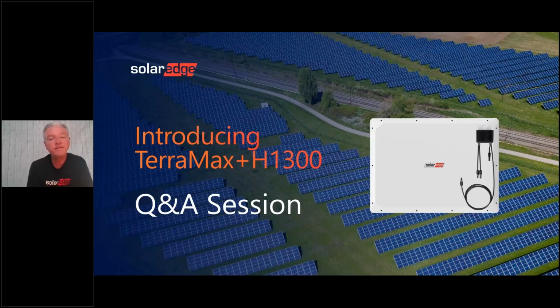Does SolarEdge have any regular maintenance scheduling advice? I would assume this is for things like fans getting clogged up with dust and just checking on the inverters. Yeah, so one of the benefits of our system is that our monitoring program can give you alerts on a number of different things. For instance, we monitor the temperature of the AC and DC terminal blocks. And if they get too high, which we have found is an early indicator of failure, it alerts to the monitoring portal and alerts you that you have to visit the site and do some kind of maintenance or check it out.